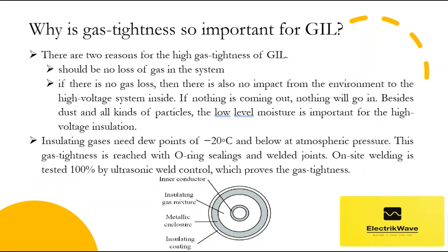Why is gas tightness so important for GIL? There are two reasons. First, there should be no loss of gas in the system, because it is needed to keep the insulation of the high voltage and to stay in operation. Second, if there is no gas loss, then there is also no impact from the environment to the high voltage system inside — if nothing is coming out, nothing will go in. Besides dust and particles, low-level moisture is important for high voltage insulation; insulating gases need dew points of minus 20 degrees Celsius and below at atmospheric pressure. This gas tightness is achieved with O-ring sealings and welded joints, and on-site welding is tested 100% by ultrasonic weld control, which proves gas tightness.